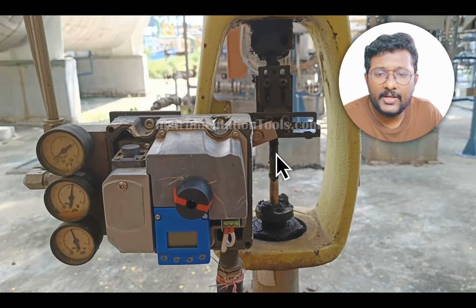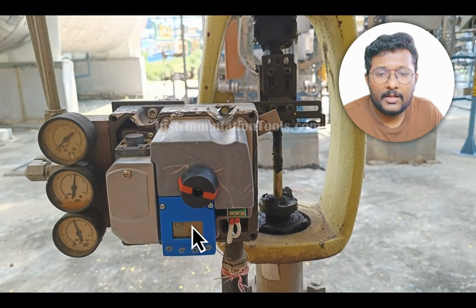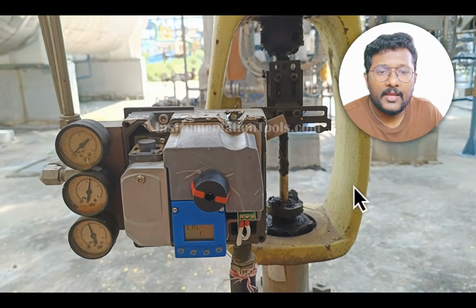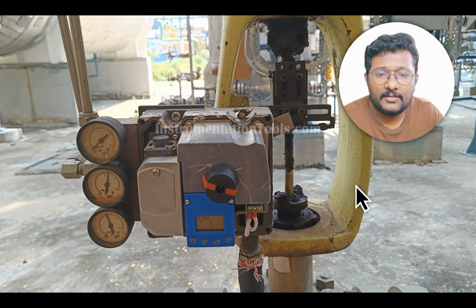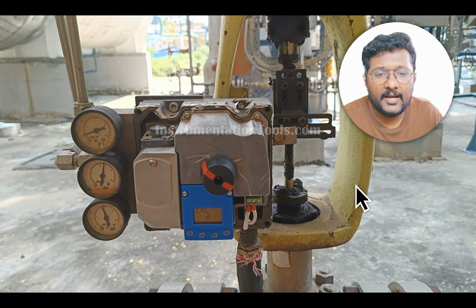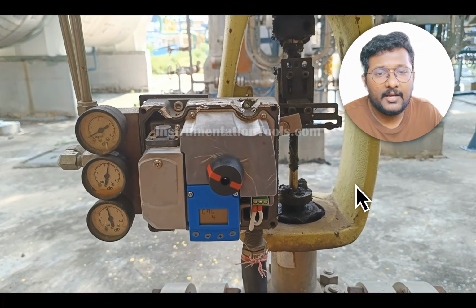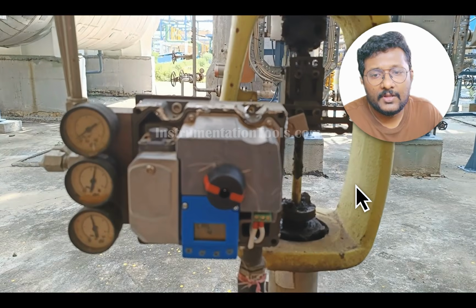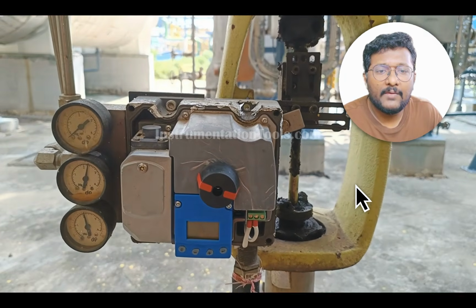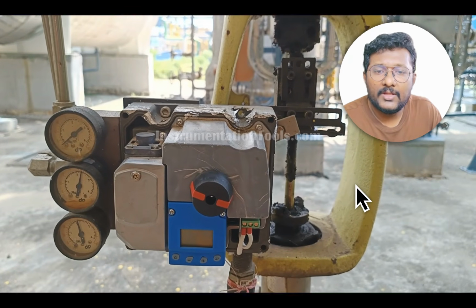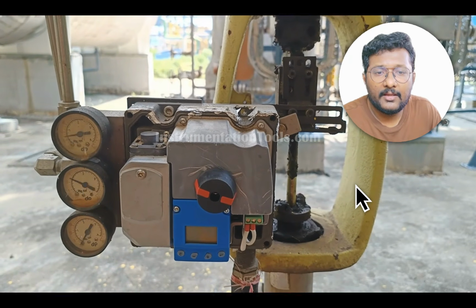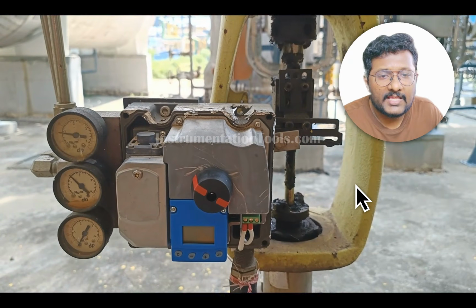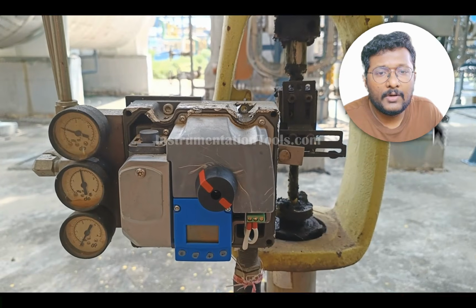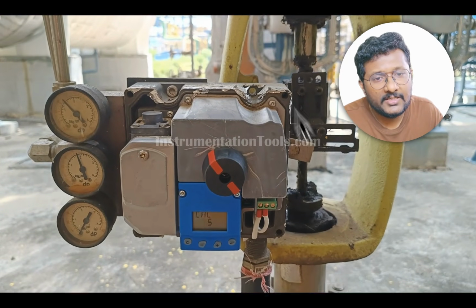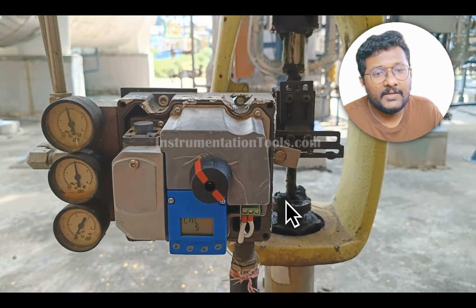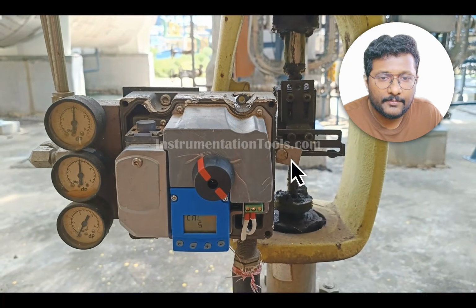Remember, you can see the calibration status on the display. Now it is showing cal 1. It has to reach cal 100. Whenever it reaches cal 100, that means the automatic calibration is completed. See, the valve positioner has an inbuilt algorithm so that when we select automatic calibration as per the algorithm, it will move the valve stem at different locations, that means different points, and then it will adjust the feedback accordingly.